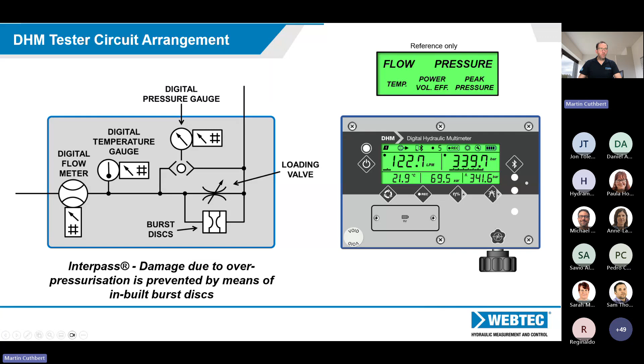Let's just talk a bit more about the Interpass system. This is a cut through the flow meter underneath, and there we have the two burst discs inside. We supply spares inside the tester in case they fail. The advantage of this system is that if you were to overpressurize the system above what the discs are rated to, as standard that's 420 bar, then the discs rupture and the oil just passes through the middle of the load valve. So it doesn't matter how much the load valve was turned in, it will just take the path of least resistance through the center of the load valve, through the burst discs and out the back.